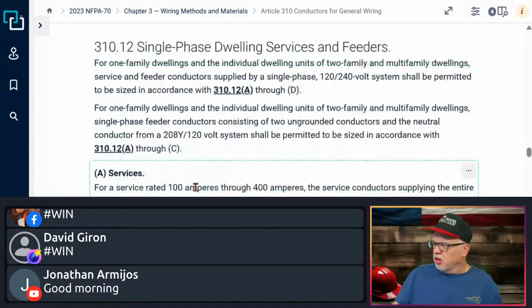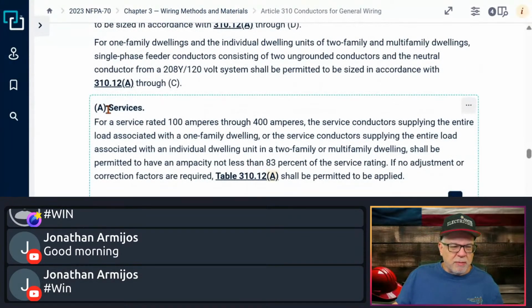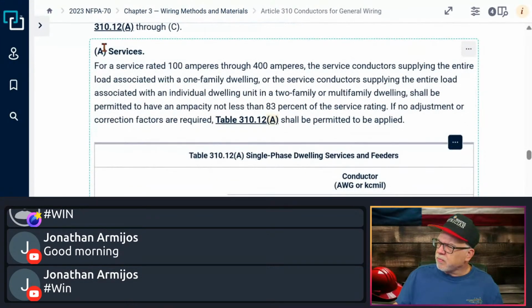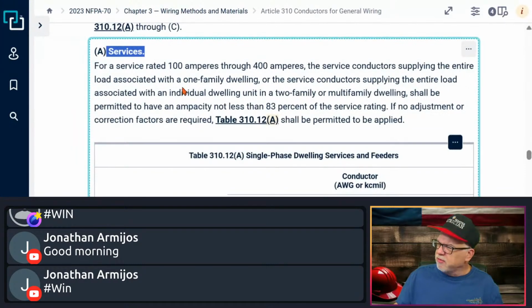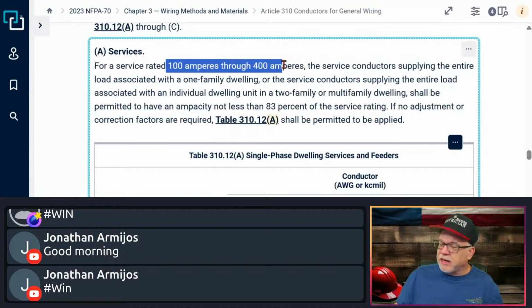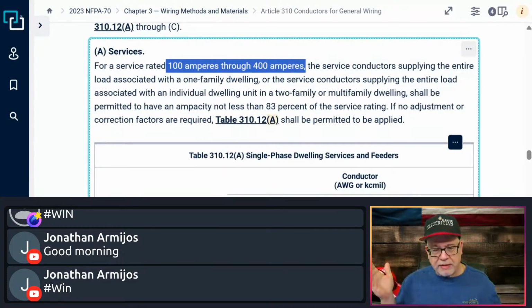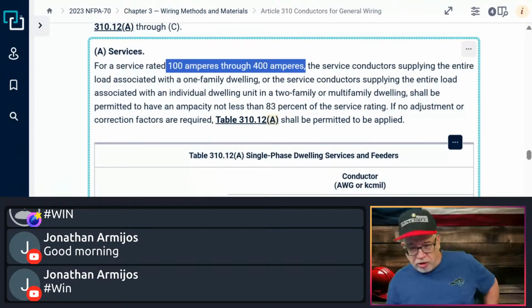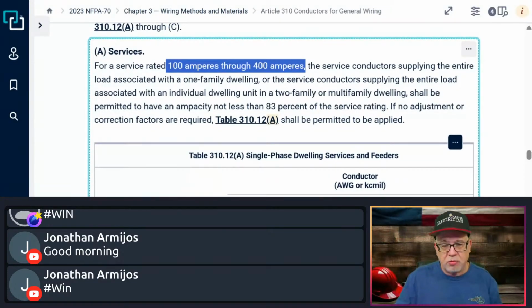All right. So here's that service we were talking about right here, using 310.12. There's A for services. It's got to be within 100 to 400. And again, I'll remind you, it doesn't matter whether you use a standard method or the optional method. Whatever gets you between that 100 and 400 amps will trigger whether or not you get to use 310.12. It's not specific to the standard method. Okay, that's another misconception that people have.